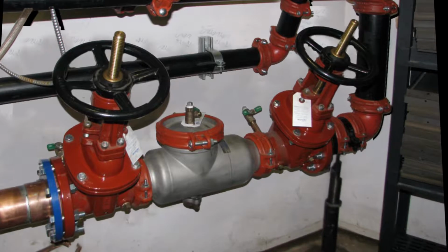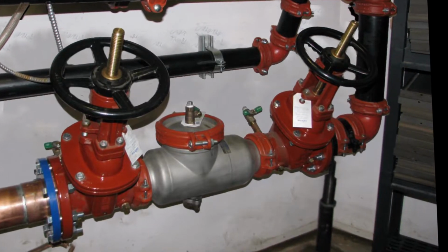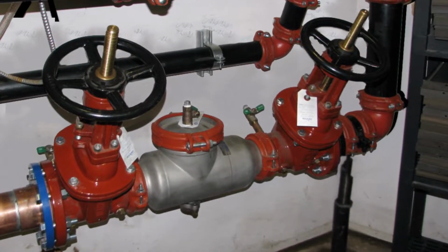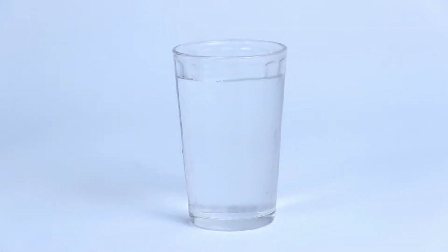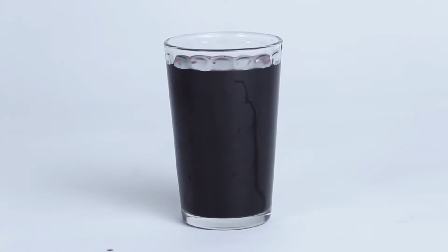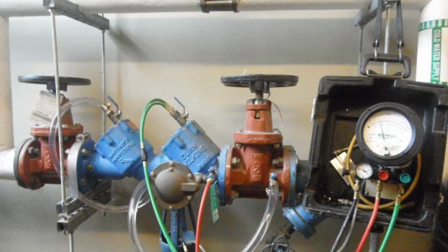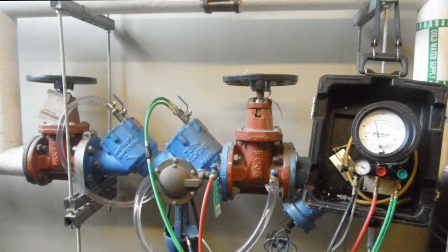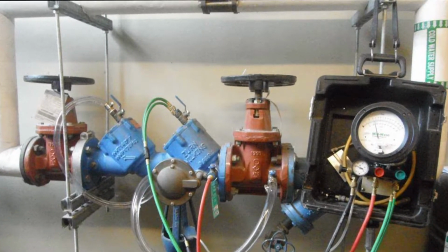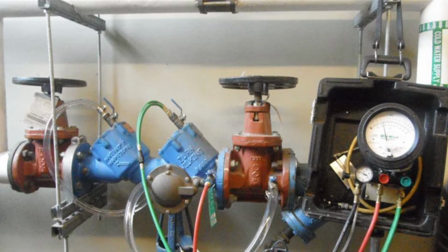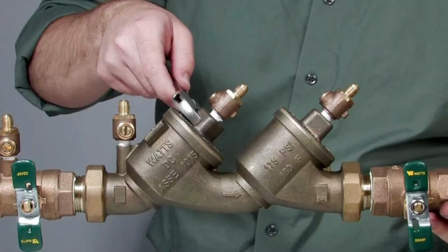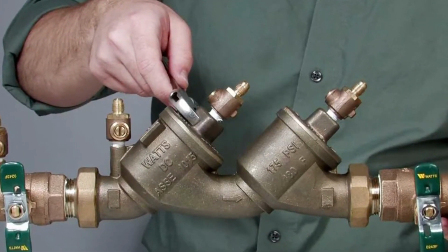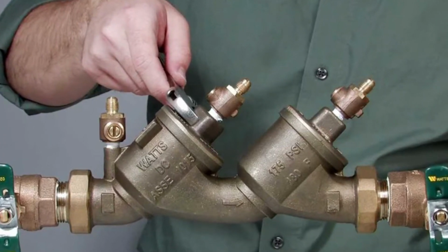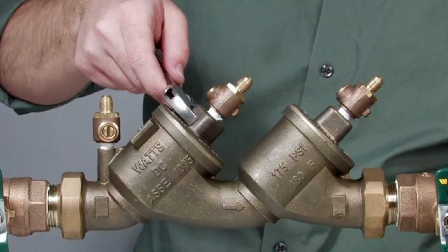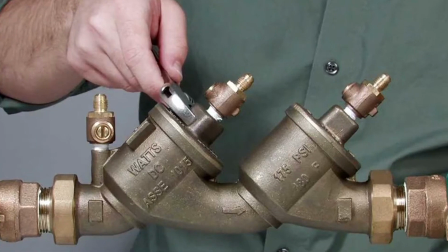The purpose of the backflow preventer is to make sure that when the city water goes through the pipes, both the clean drinking water and dirty sprinkler water do not mix together. You need to have specific test equipment for this to be tested. There will be gauges with hoses, and once the hoses are plugged in, the test will measure the flow of the water in valves. Believe it or not, you need to have a certificate approved by the proper authority in your municipality to be able to conduct this type of test.